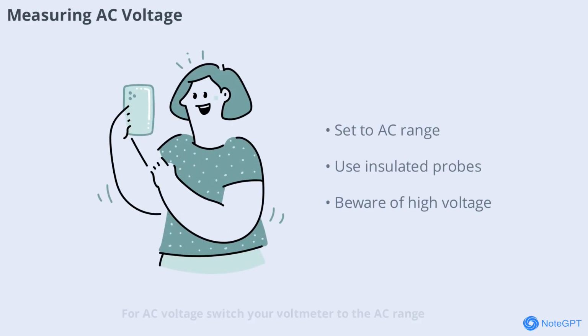For AC voltage, switch your voltmeter to the AC range. Connect the probes to the 2 points where you want to measure the voltage, such as wall outlets or AC circuits. The voltmeter will display the root mean square, RMS, value of the AC voltage. Be extra cautious when measuring AC, as these voltages can be dangerous. Always use insulated probes and keep your hands clear of live wires.